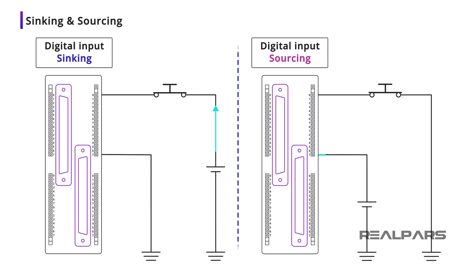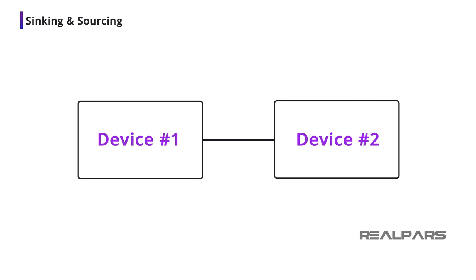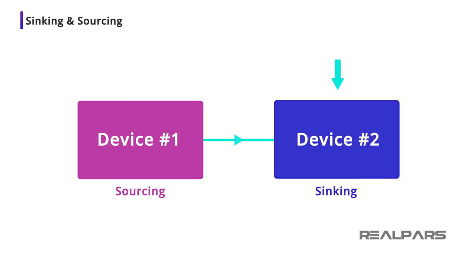Let's spend some time clearing up any misconceptions you might have about these terms. When we talk about sinking and sourcing, it's all about defining the direction of conventional current flow between two devices. Think of it this way: current is flowing between device number 1 and device number 2. The current is flowing from device number 1 to device number 2. Therefore, we say device number 1 is sourcing the current and device number 2 is sinking the current.